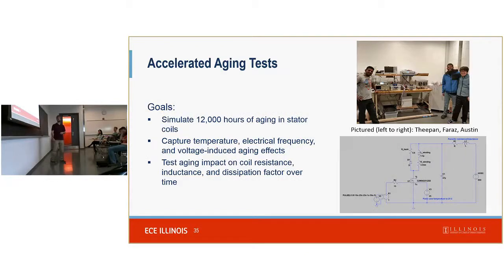Now talking about winding qualification, how do we know that the windings we build actually work? They do what they're supposed to do, and the insulation is sufficient is a big question. So one part of that has been accelerated aging testing. With accelerated aging testing, that's applying higher frequency power to the coils at a higher temperature. And by doing those two things, we can simulate really rapid aging of the insulation. At the end of running through this test, the idea is to get a good idea of if the insulation will actually last an acceptable lifetime.